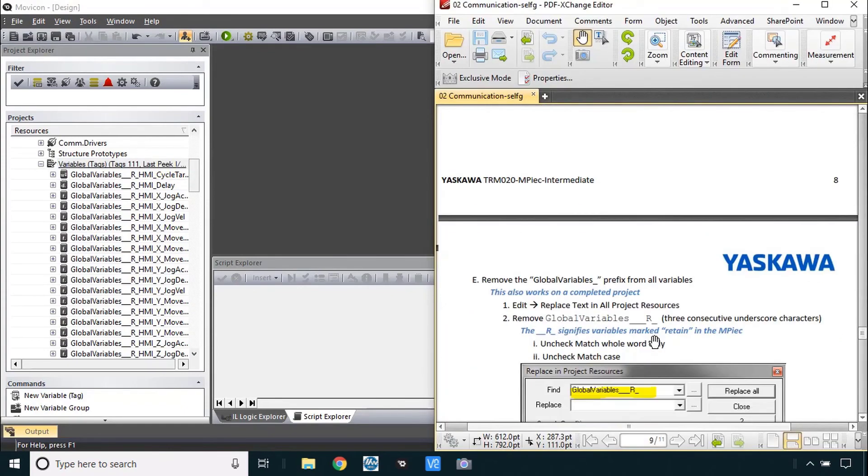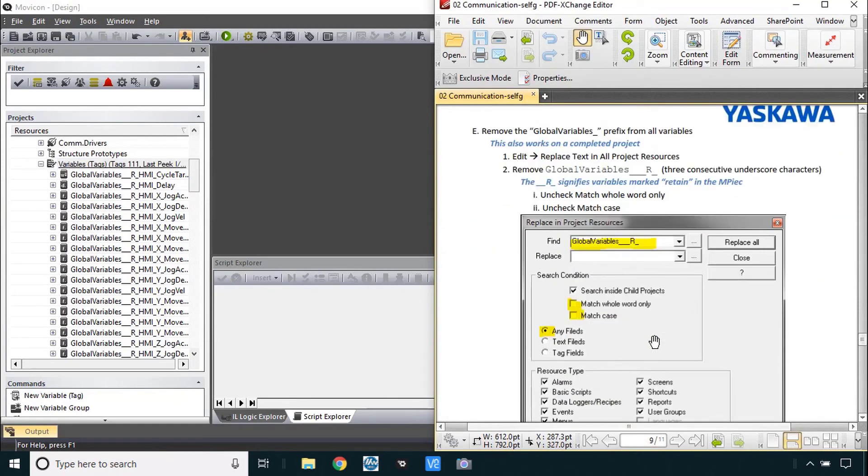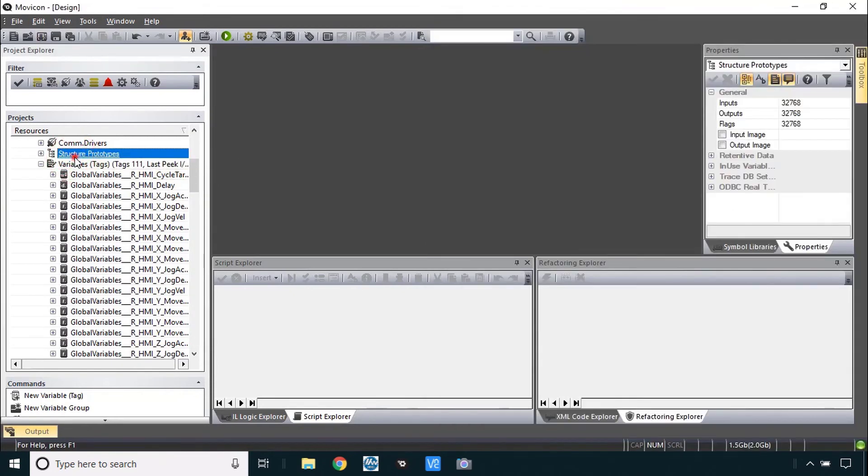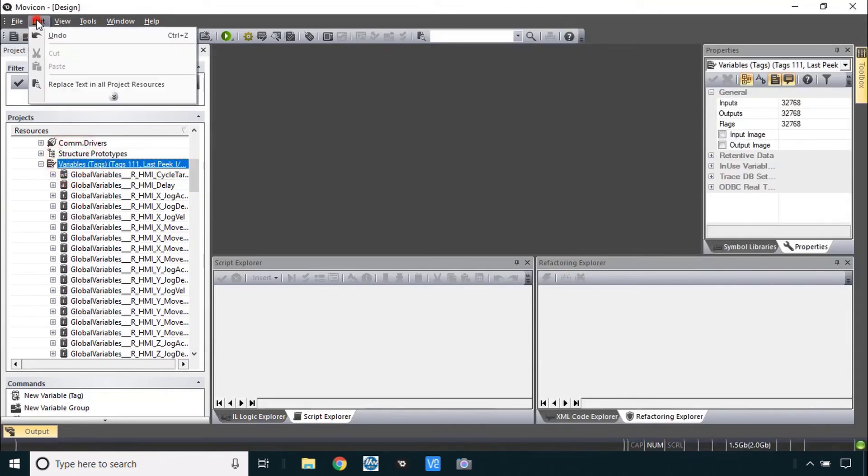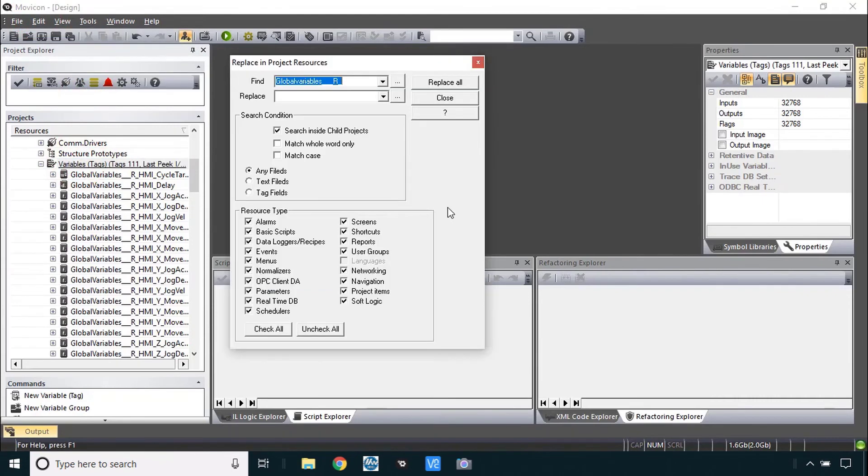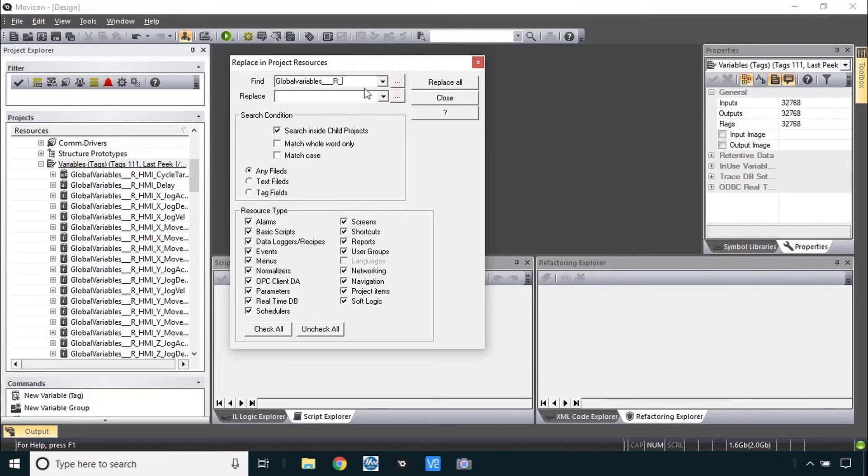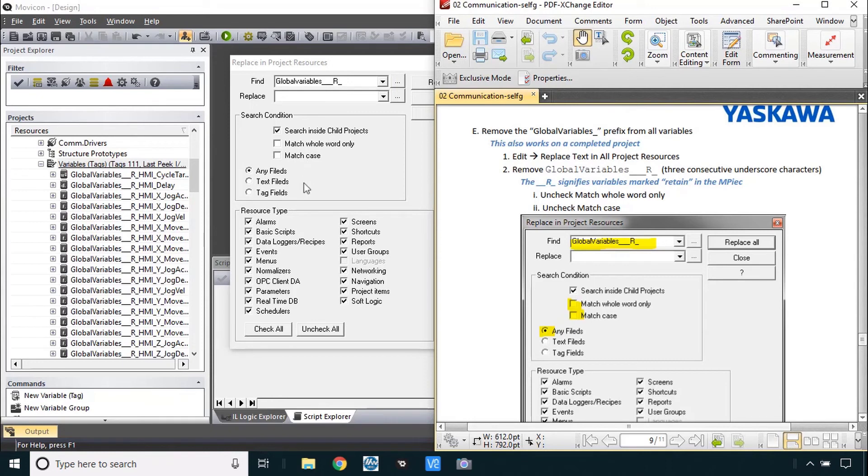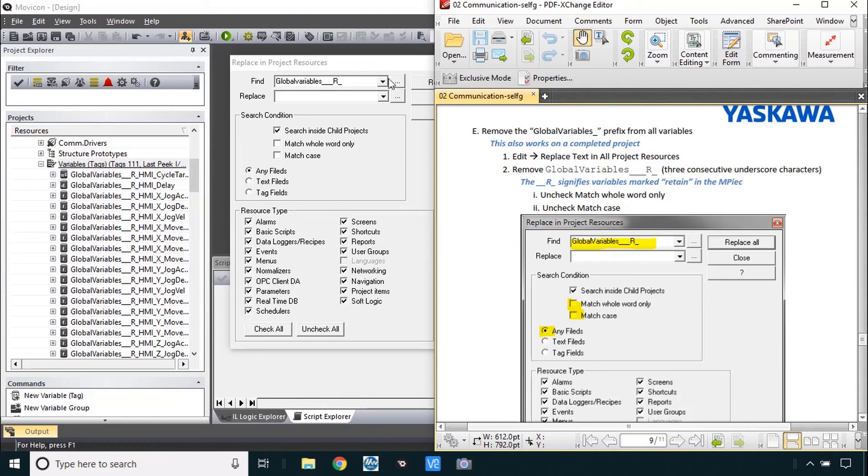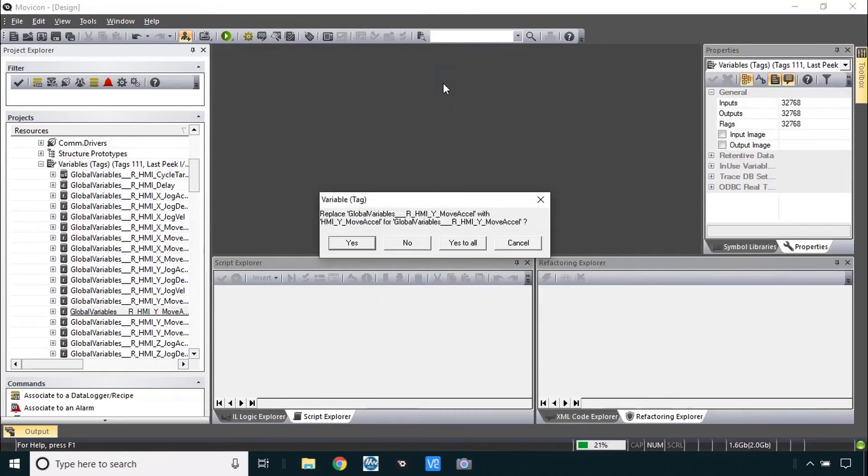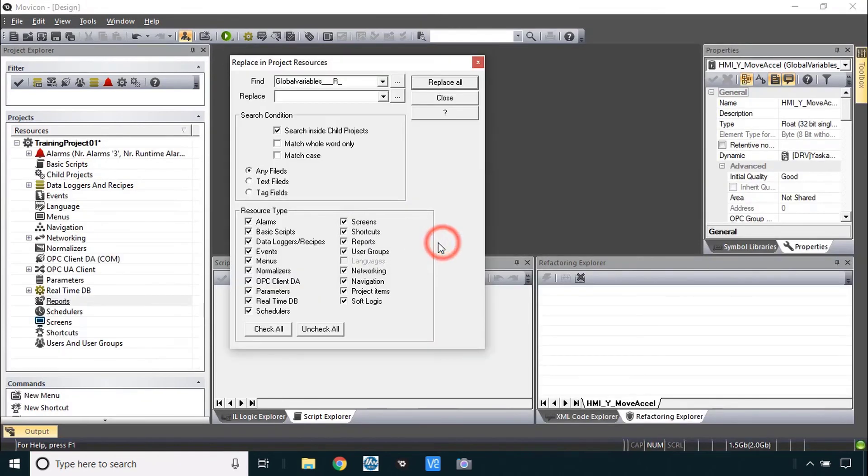But the next step here is to remove that global variables prefix by using edit replace text in all project resources. Be sure you're in the project tree. And go to this edit replace text in all project resources. What I do first is to get rid of these retained prefixes. That's global variables three underscores R and another underscore. Type that in here. Replace it with nothing. You do want to check those fields. Be sure that you don't have match whole word only or match case. You just want to find this text in any of the variables. And this tool is kind of nice because you can use it even after you've programmed your HMI with these default names. You could still replace in all project resources and it would update them all. OK. So we've got that set here. And replace all. Yes to all. 23 of those.